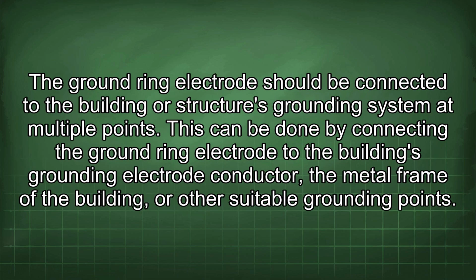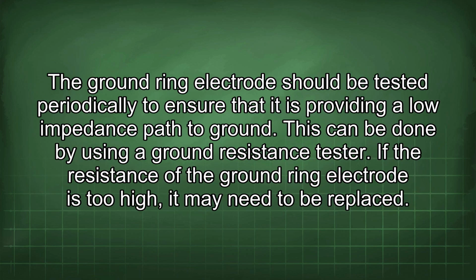The ground ring electrode should be connected to the building or structure's grounding system at multiple points. This can be done by connecting the ground ring electrode to the building's grounding electrode conductor, the metal frame of the building, or other suitable grounding points. The ground ring electrode should be tested periodically to ensure that it is providing a low impedance path to ground. This can be done by using a ground resistance tester. If the resistance of the ground ring electrode is too high, it may need to be replaced.